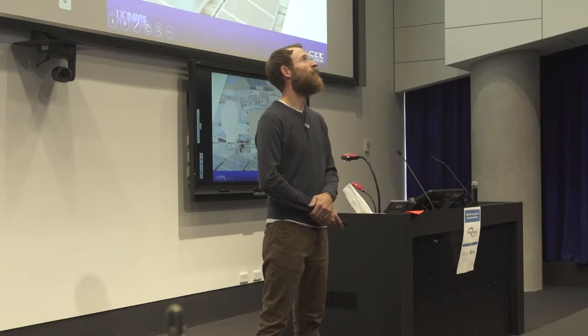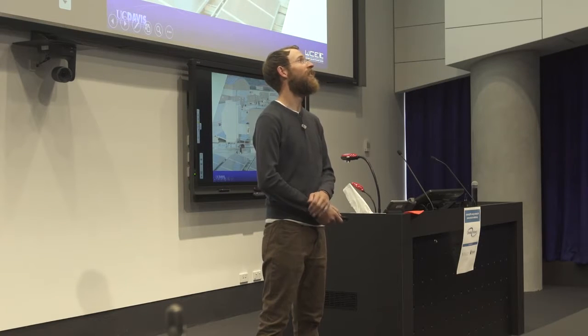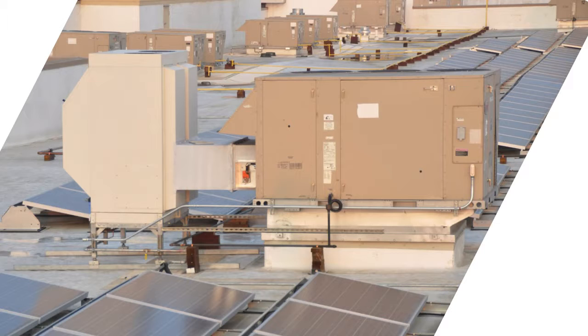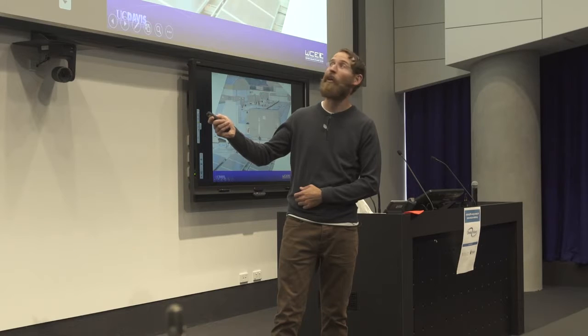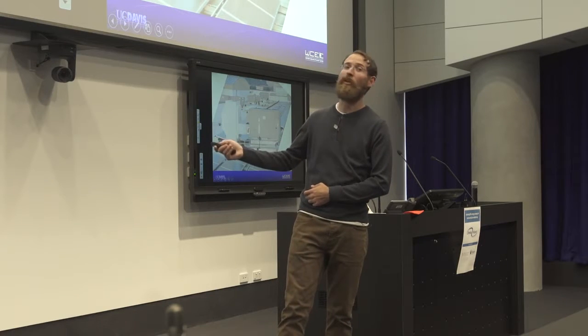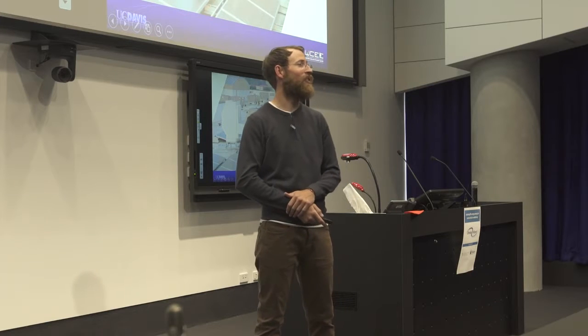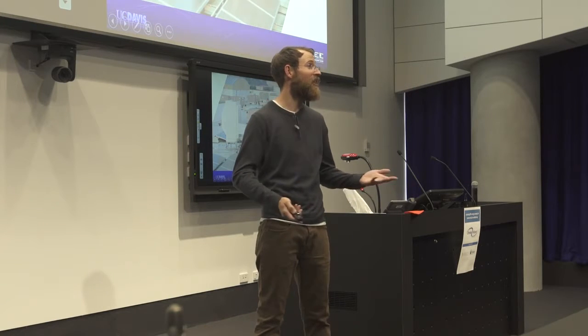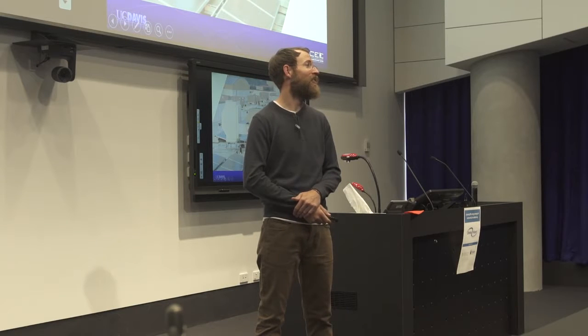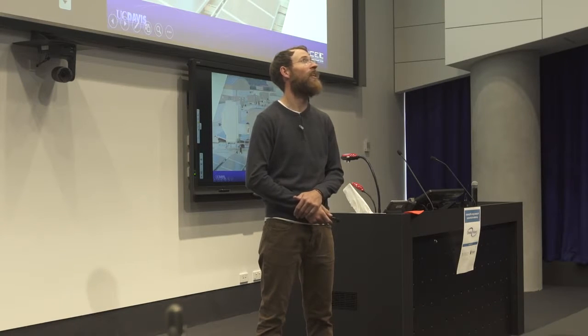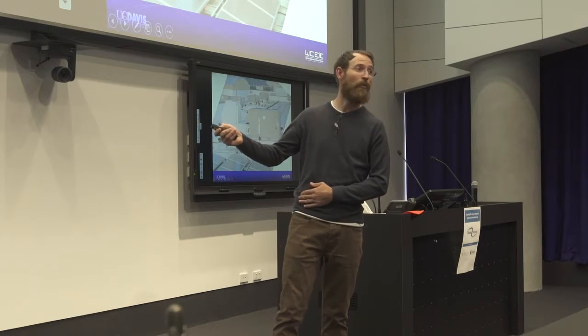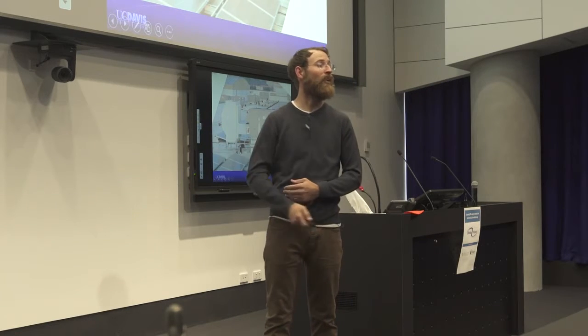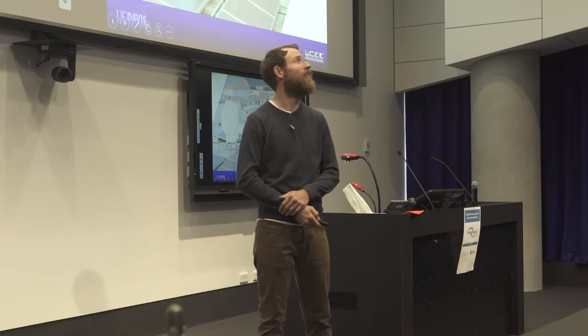This is what the packaging looked like. We set these up on the rooftop so that all of the indirect evaporative coolers were sized to provide enough ventilation for the entire store, and they were set up in a way that delivered the product air, or the supply air, from indirect evaporative cooling through the rooftop air conditioner and down into the store, which gave us some major advantages in that we used the existing ductwork. It was a very simple installation, if you will, because we didn't have to do any roof curb adaptations, no new penetrations into the rooftop, no new ductwork runs and things like that.